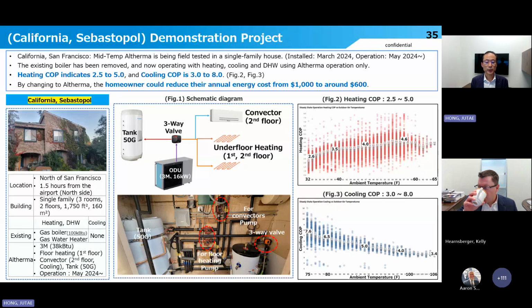As you can see from figure 2 and figure 3, the average heating COP was around 2.5 to 5.0, and cooling COP was around 3.0 to 8.0. By changing the gas boiler and gas water heater to Daikin Altherma, they could reduce their annual energy cost from $1,000 to around $600. We also received some feedback from the homeowner.